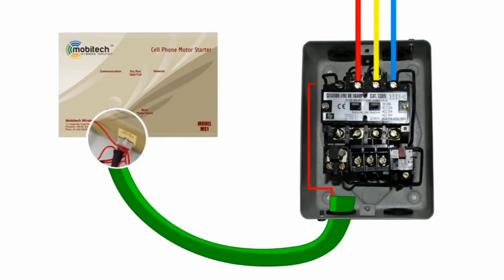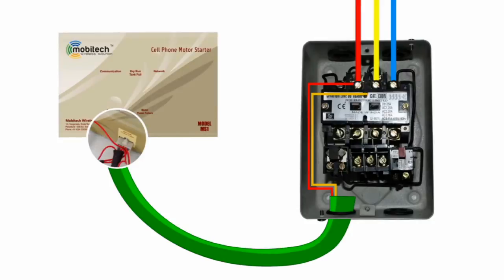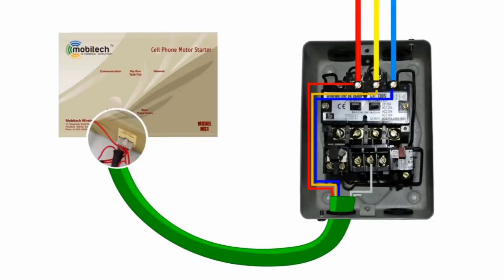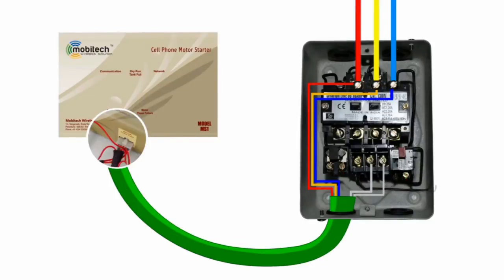Connect red wire to R phase, connect yellow wire to Y phase, connect blue wire to B phase. Connect gray color wire to motor output. Remove black wire which is indicated in this video, then connect green wires into ON screw.